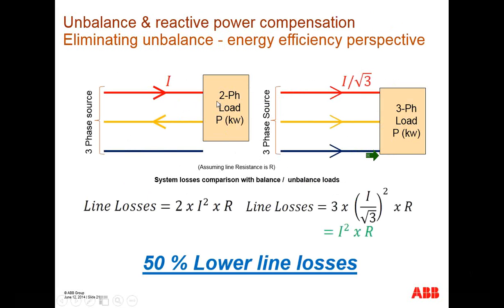Here is an example of how the unbalance is affecting the network. Suppose you have a two-phase load, and the losses are 2 times I square R system losses. If this load is divided into 3 phases, the same current will fall by I by root 3. So losses will be 3 times I by root 3 square into R, which means the root 3 and 3 get cancelled. So it becomes I square R. If we make it a balanced system, then the losses are drastically reduced in the system, and thereby upstream also in the distribution and transmission line.